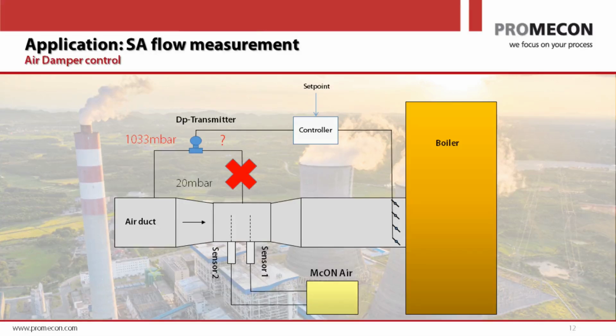You have two pressure points, one before the venturi and one inside the venturi throat. And if you measure these two pressures, the static and the dynamic pressure, the dP will be an indication of your flow in a way that the square root of the dP is proportional to airflow. Very simple principle, very elegant, and works very, very nicely. However, in the coal-fired power station, it's different. In the coal-fired power station, you get a problem.